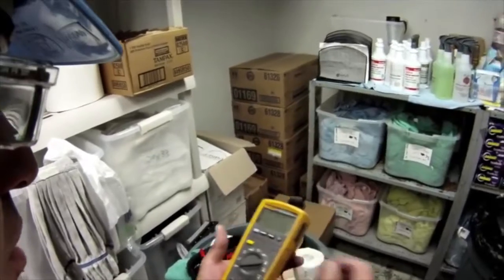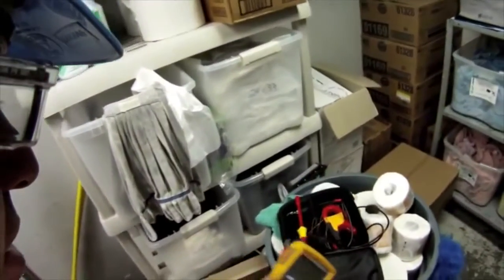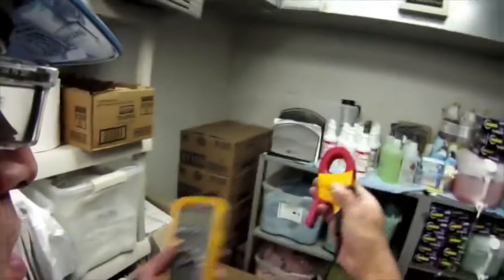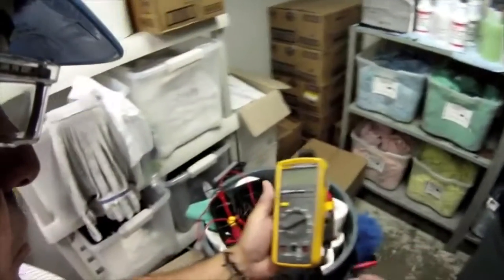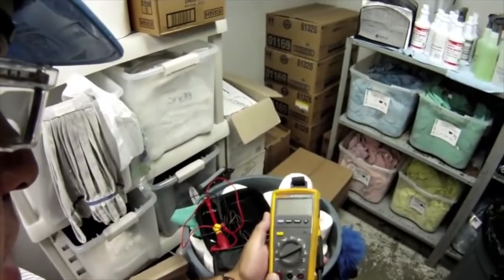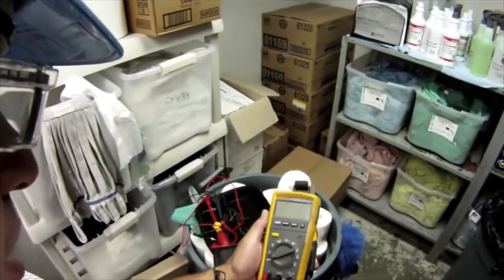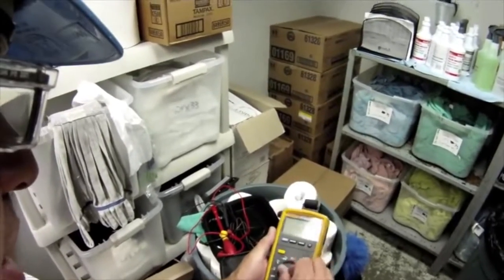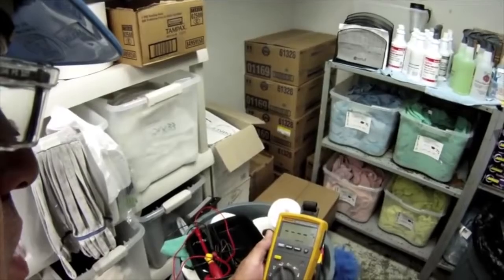And so for now I'm going to turn that off, take these test leads off, and then I'm going to put on my clamp attachment. So I'm testing amps. So my red lead goes in the amperage, my black lead goes in the common. I'm going to test this on a millivolt scale. And now I'm set up, I'm ready to go on a millivolt scale, and I'm going to go back inside to the compartment and find that black lead right there. I'm going to clamp onto it.